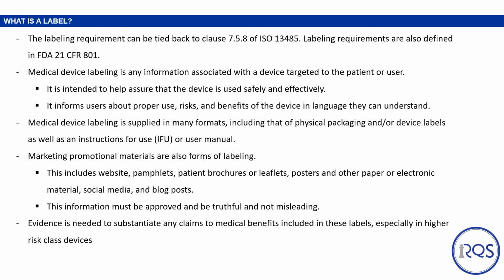Let's first start out with defining what a label is. The labeling requirement can be tied back to Clause 7.5.8 of ISO 13485, as well as FDA's 21 CFR 801. Medical device labeling is any information associated with the device targeted to the patient or user. Labeling is intended to help assure that the device is used safely and effectively, and informs the users about proper use, risks, and benefits of the device in the language that they can understand. Medical device labeling is supplied in many formats, including that of physical packaging and/or device labels, as well as IFUs or user manuals.